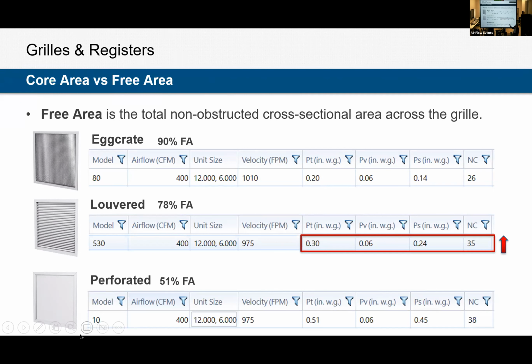Okay, so we looked at the small reduction in free area. Now we're all the way down at 51%, and we can see our static pressure is 3 times. And then our sound is up again, 12 NC. So reduction in free area, increase in pressure drop, increase in sound.